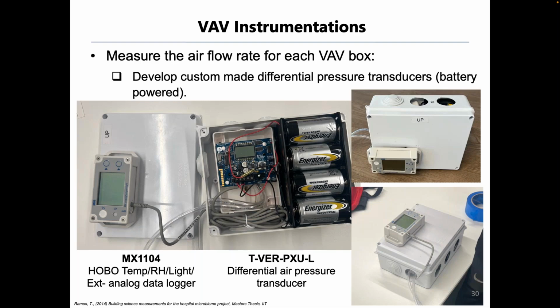Yeah, and going back to the questions about scaling, even the velocity sensors, you need to scale them. Also, in the app, you can select the instrument, or earlier I showed the previous example of my work, where the differential pressure sensor was not an Onset product, but the loggers were able to accept those scaling factors. Perfect.